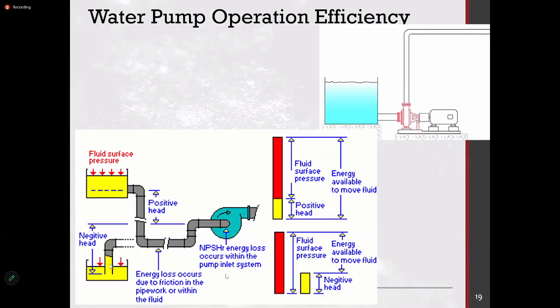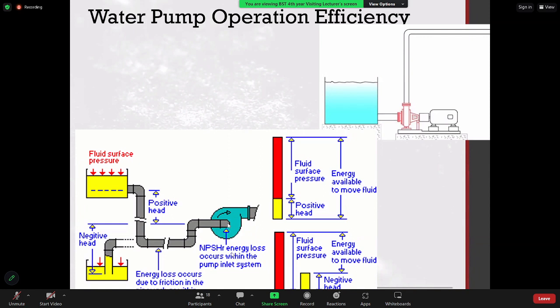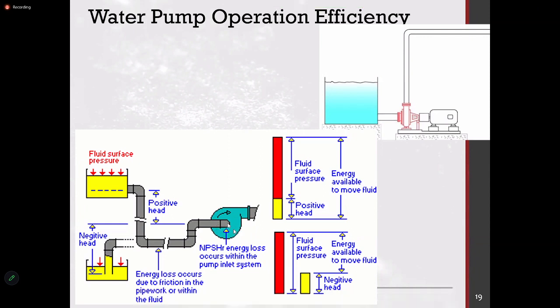what do you call it, float or the valve here, the entire water can come down, and the pump will run dry. But in this type of arrangement, you have the water coming in to the pump by gravity, so there is always water inside the pump, so the pump will not run dry. Because for pump cooling, during design, they have assumed a certain amount of cooling happens because of this water circulation. It's not an air-cooled thing, so this water is actually used to cool the pump and the motor as well, to keep it at a good temperature. So if it is running dry, or just running without water, then the pump could be damaged.